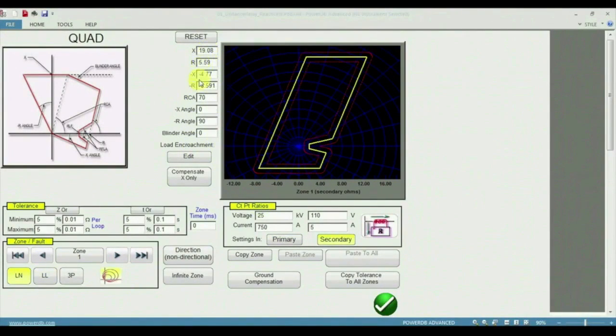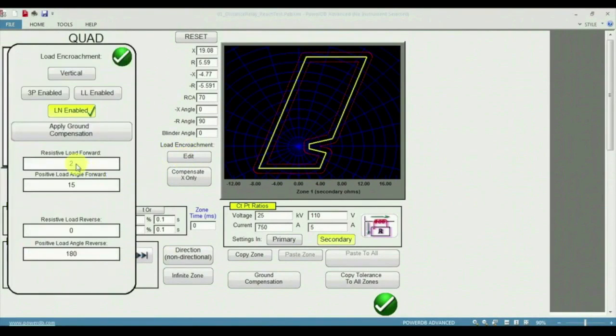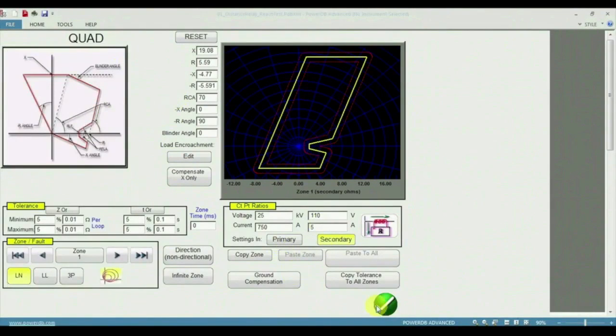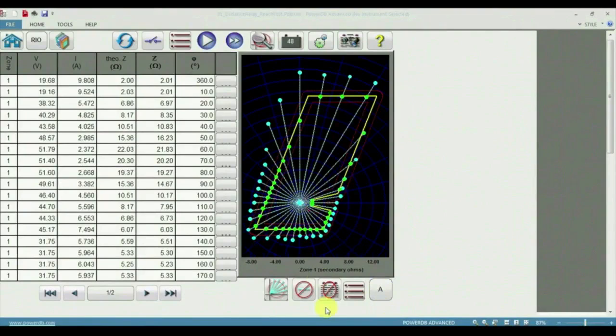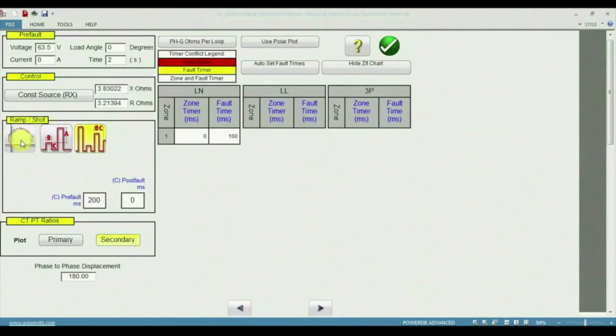Now we have entered all the values in line with the relay settings, and the load encroachment settings can be entered by clicking on this edit option. So 2 ohms and 15 degree. So once the values are entered, click on this tick mark. Click on this menu, the testing menu. So here you have 2 options. One is the shot test and other is the reach test. The shot test is used to do timing and the reach test is used to verify the boundary. So let's execute a shot test and identify the results.